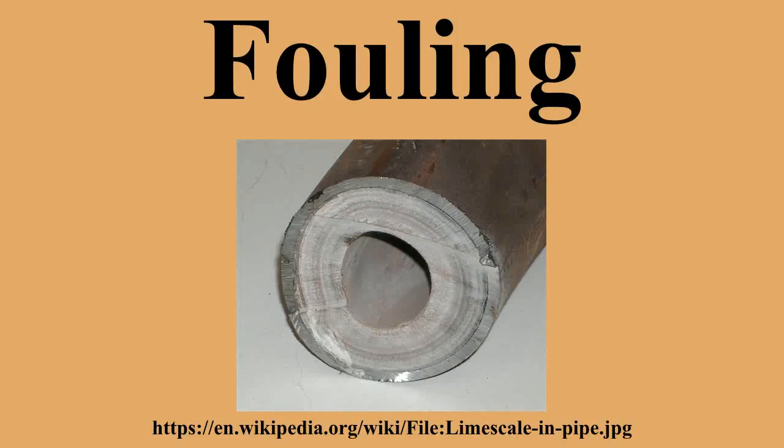In a 1,300 MW nuclear power station, typical losses could be 20 MW an hour. In seawater desalination plants, fouling may reduce the gained output ratio by 2-digit percentages. The extra electrical consumption in compressor-operated coolers is also easily in the 2-digit area, in addition to the operational costs. Also, the capital cost increases because the heat exchangers have to be designed in larger sizes to compensate for the heat transfer loss due to fouling.